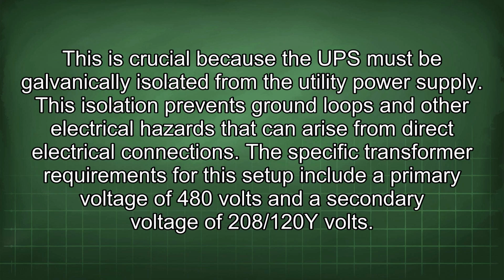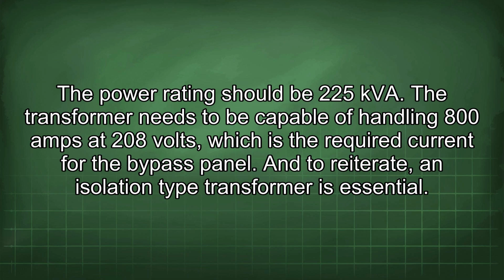The specific transformer requirements for this setup include a primary voltage of 480 volts and a secondary voltage of 208/120 Y volts. The power rating should be 225 kVA. The transformer needs to be capable of handling 800 amps at 208 volts, which is the required current for the bypass panel. And to reiterate, an isolation-type transformer is essential.